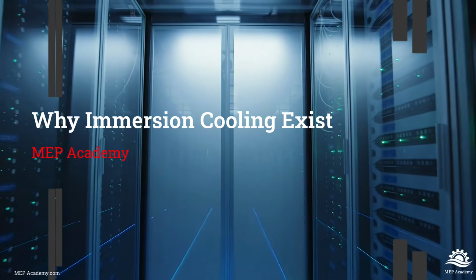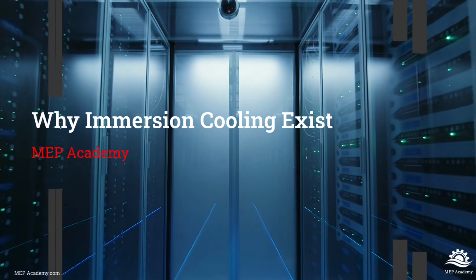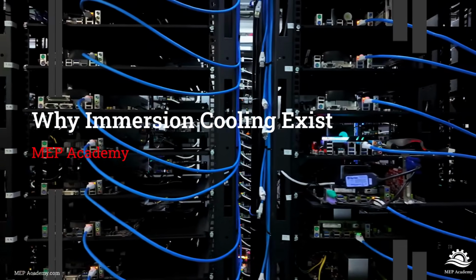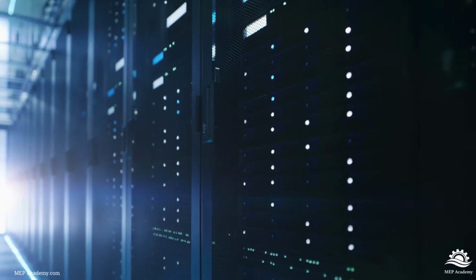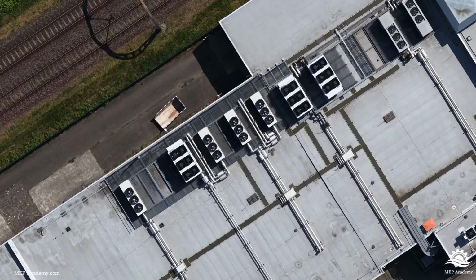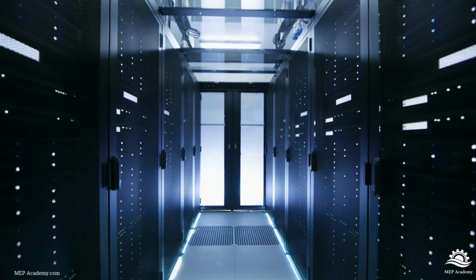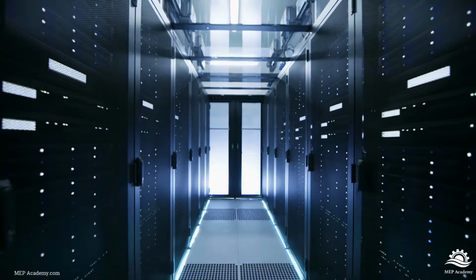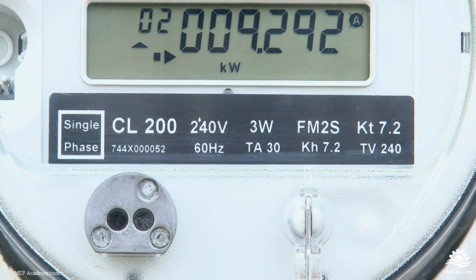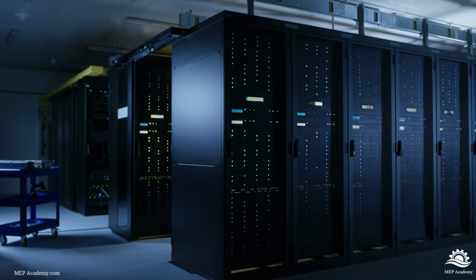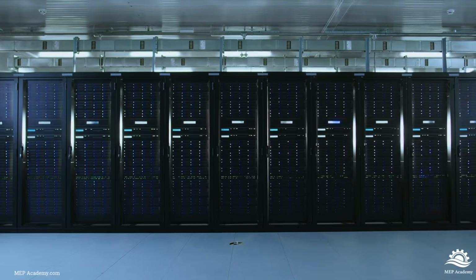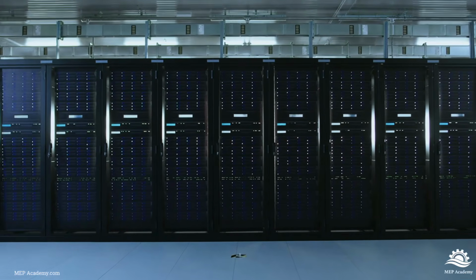For decades, data centers have primarily relied on air cooling. Cold air is delivered to the front of the server. The server fans pull that air through the equipment. The air absorbs heat. Then the hot air is removed from the room. This worked extremely well when server racks consumed 5 to 10 kilowatts. Then racks increased to 20 kilowatts, then 40, then 60. Today, many AI deployments exceed 100 kilowatts per rack. Some are approaching 200 kilowatts and beyond.